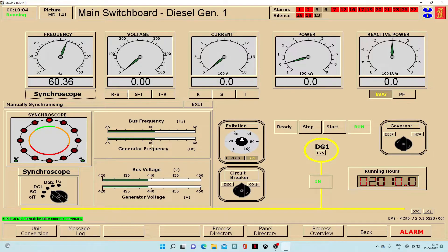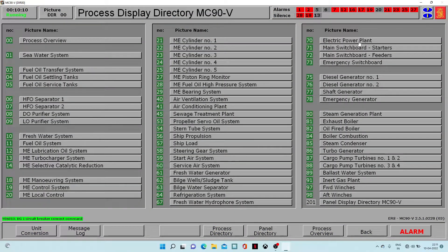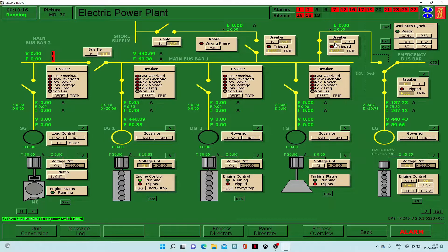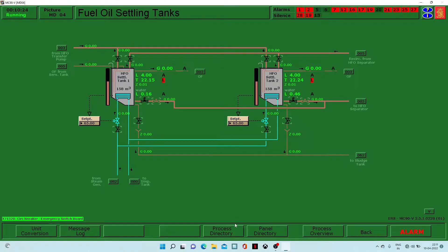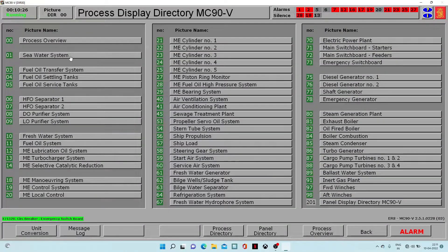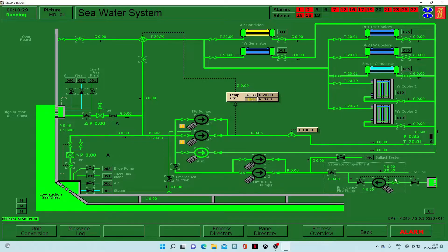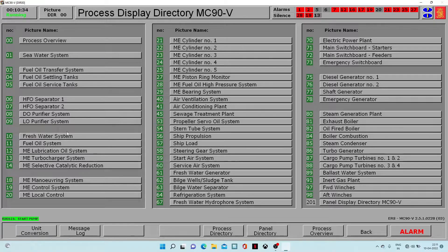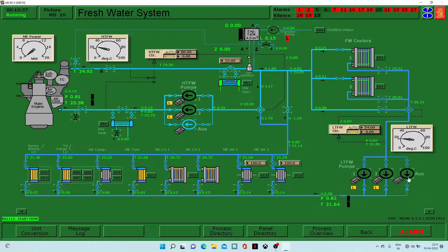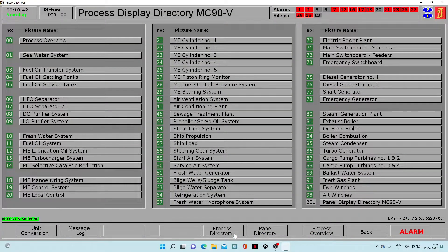Both green lines are aligned on both parts, which means it is well synchronized. We go to the electrical power plant and turn on the breaker. After turning on the breaker, always remember that the two sea water pumps will close automatically, so we have to turn them on again — one pump here and another one there. After restarting those two pumps, diesel generator one is running and connected to the bus bar.